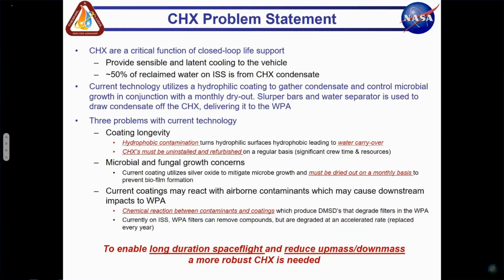The current technology that we use to control the sensible and latent cooling uses a hydrophilic coating to gather condensate and control microbial growth, in conjunction with a monthly dry out. As that water condenses, it wicks out onto the surface because of the coating, and then there are slurper bars embedded into the heat exchanger that suck that water out in conjunction with an active water separator.